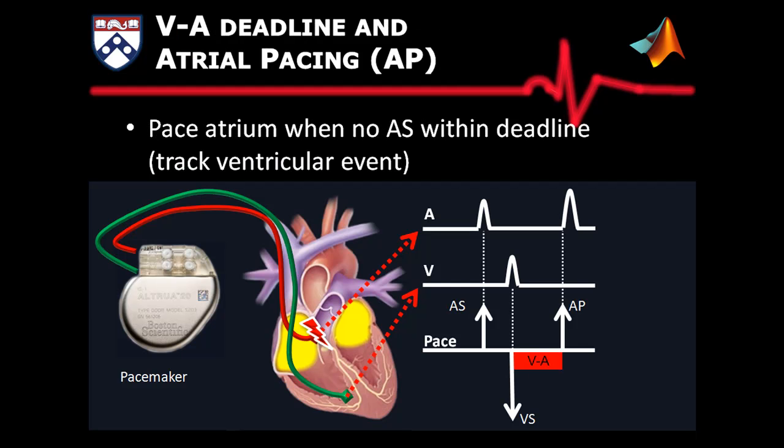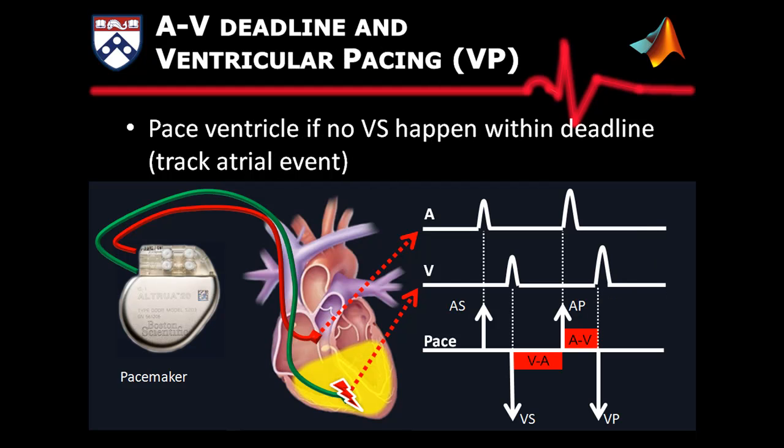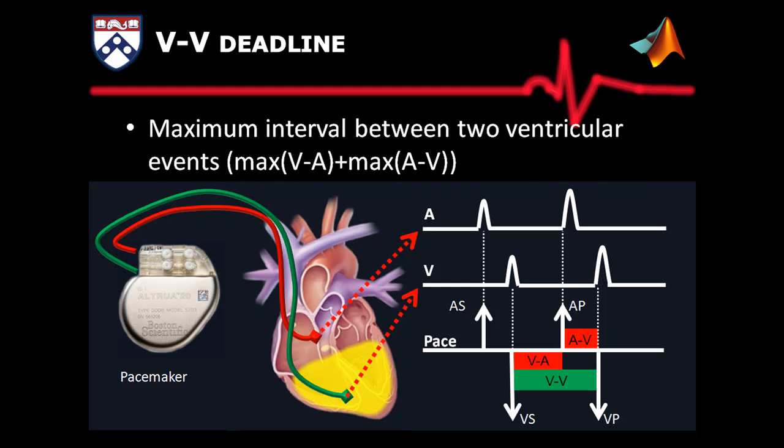After a ventricle event, if there is no atrial sense event within a VA deadline, the pacemaker will pace the atrium. After an atrial event, if there is no ventricular sense within an AV deadline, the pacemaker will deliver a ventricular pace. Both deadlines combined will ensure a maximum interval between two ventricular events, thus maintaining the heart rate above a certain threshold.